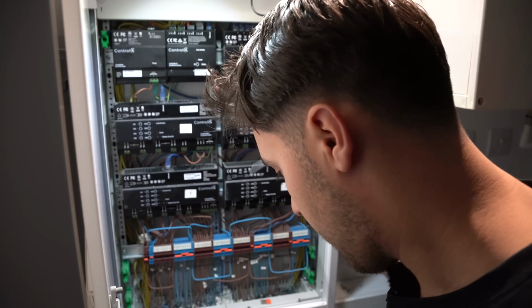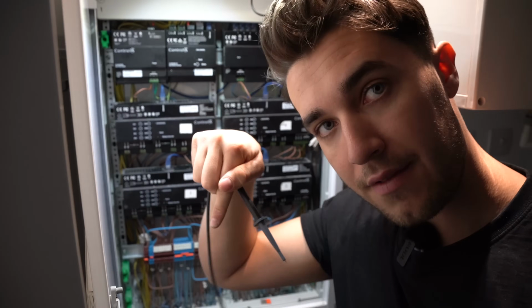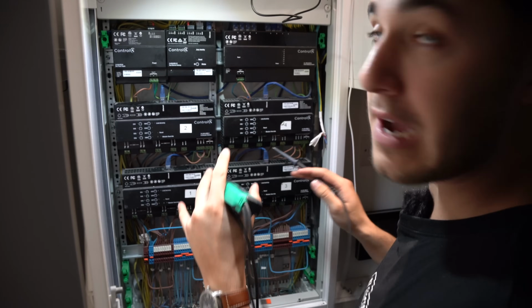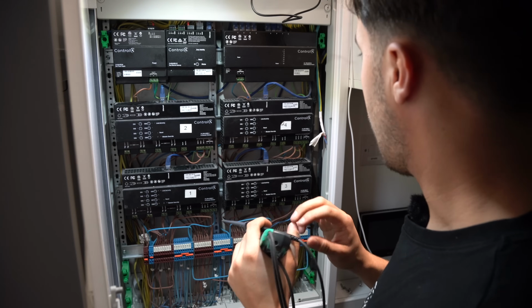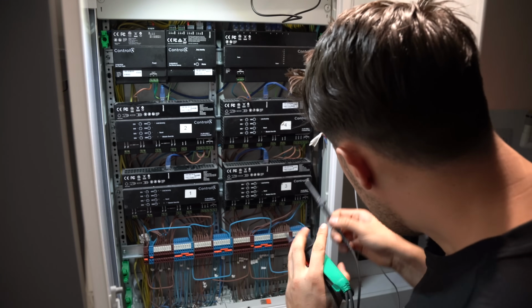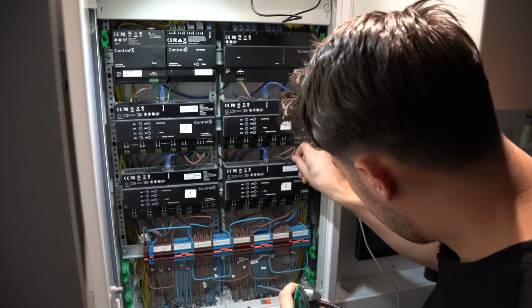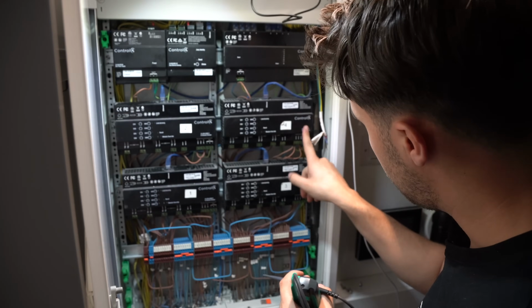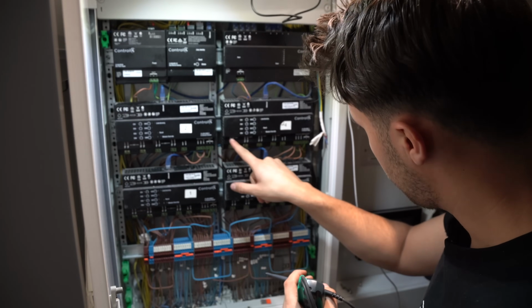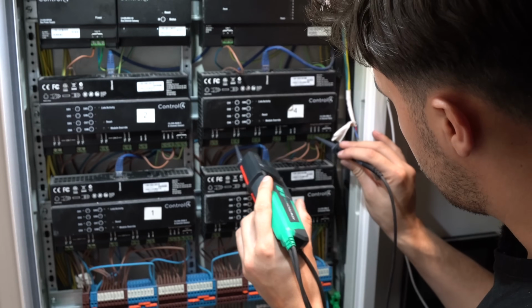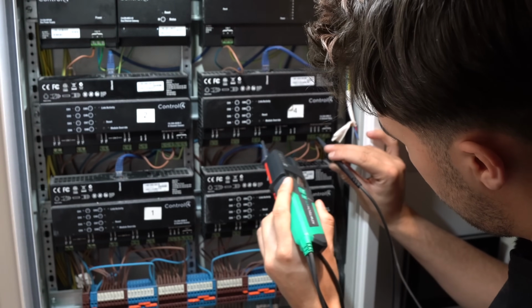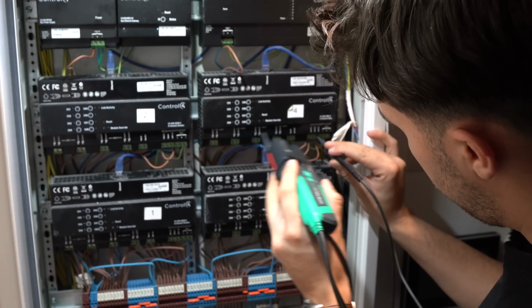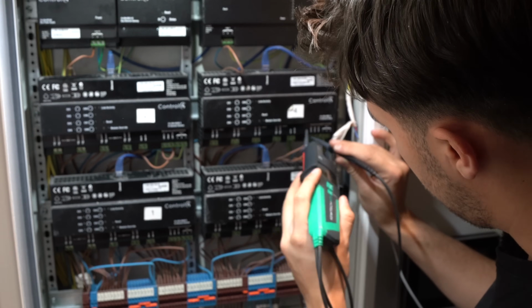Right, so this is a bit fiddly. Let me explain exactly what is going on here. So I've got the enclosure and everything ready down there for surge protection. While we've got the power off for the lights, there's some other things I'm going to take care of for this control. So how it works, these different dimmers, you've got the actual line in here, and this is the actual supply which feeds the dimmer unit itself, and it also feeds line one. Each other one of these corresponds to this terminal here, so line two corresponds to line two, line three to line three, line four to line four.